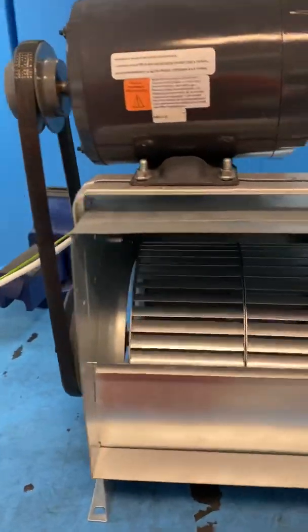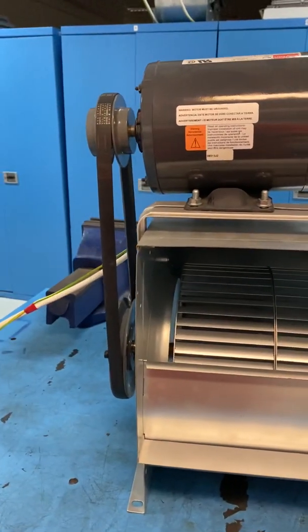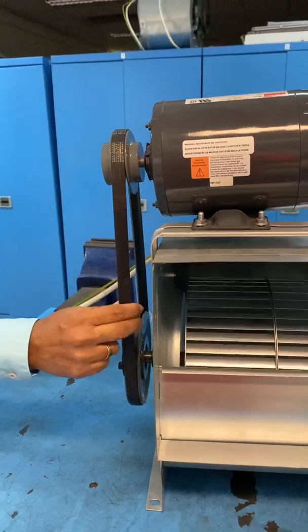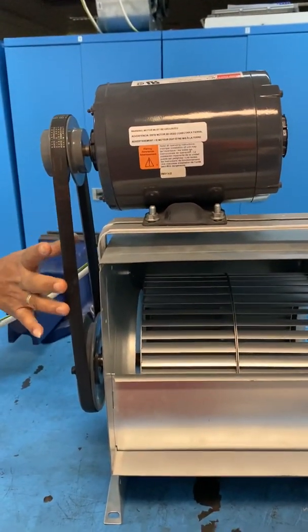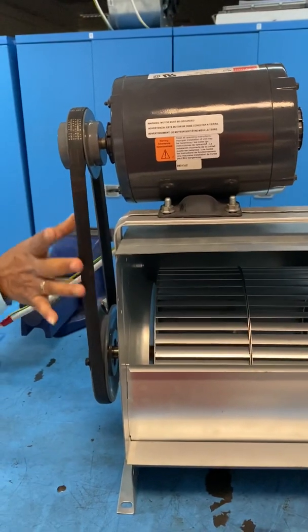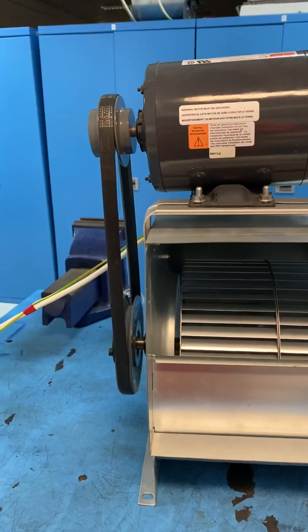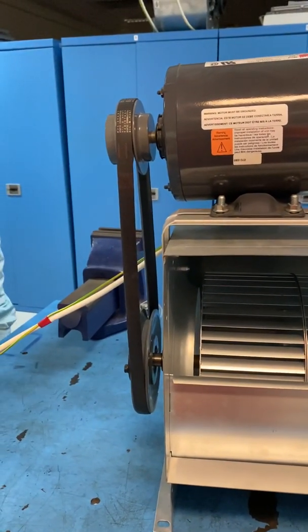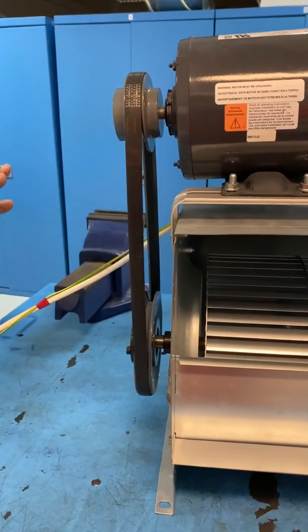So we are seeing, when this is operated, you might have noticed the tension of the belt is not correct. You need to take it out and first check the belt for any damage or crack, and then test according to the specification. You must tension the belt, otherwise the performance of the blower will not be as per the specification. That's why you need to adjust the tension. Otherwise, there will be noise.